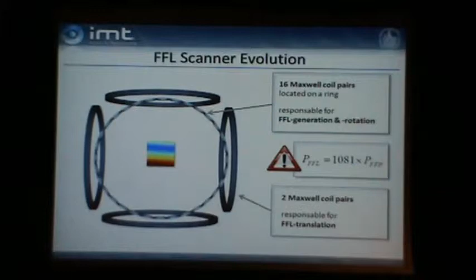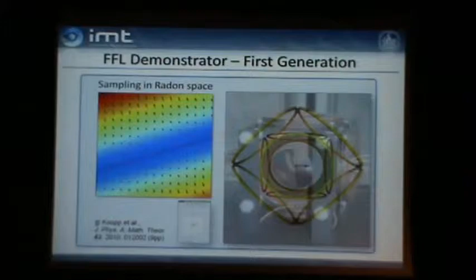However, you need some 32 coils to produce and rotate a line. And the authors then say this is impossible to produce because it's 1,000 times the power loss of a field-free point. But then, fortunately, I had an excellent PhD student, Tobias Knopp, at this time, and he proved that actually 3 coil pairs are enough to produce a field-free line, and 4 coil pairs produce an optimal field-free line. And he could show that power is then reduced to only 1.4 times that of the field-free point, and this is the point where we said, okay, then we can realize this. And actually, what we did is we did this first demonstrator in the publication of 2010.